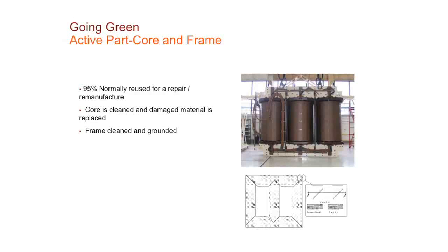The core typically, if there are any problems with it, we can actually unstack it and wipe it down. If there are parts that have any burn marks or whatever, we can actually replace parts of the core. But most of the time, we can unstack the core, wipe it down with non-conductive solvent, and reuse it. The frame is also typically reused for transformers, along with the core. We'd remove the windings, unstack the core, and reuse the frame as well.